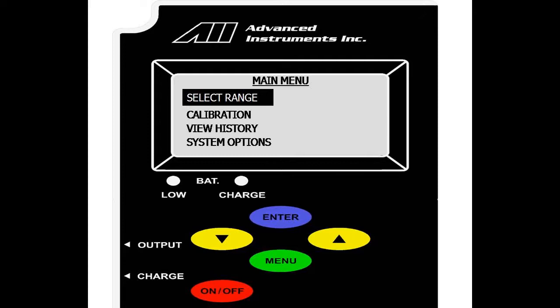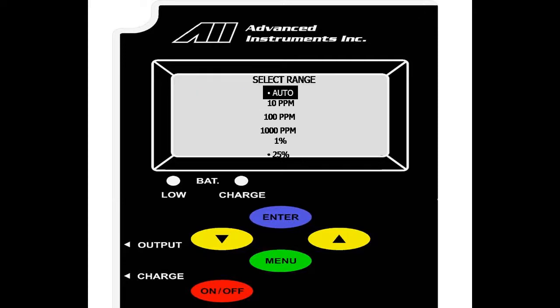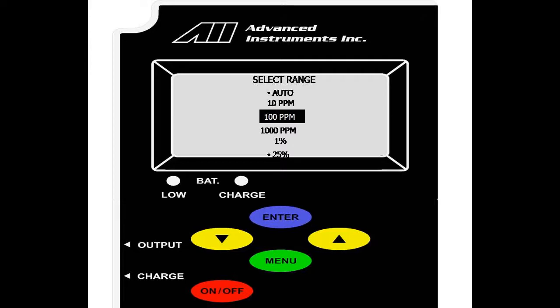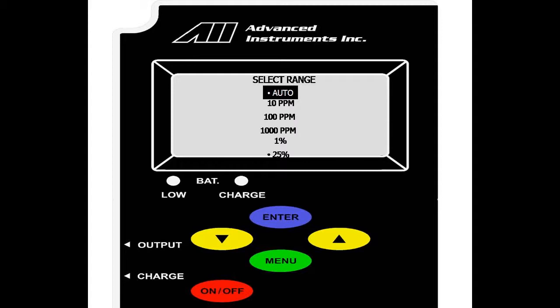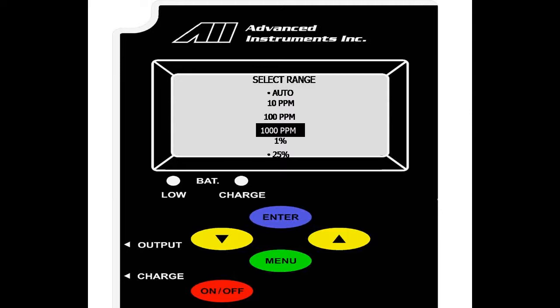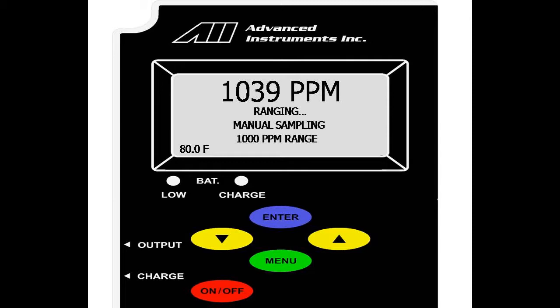We will now go over the range options. On the main menu, go to select range and hit enter. As you can see here, we have the five standard default ranges: 10, 100, 1000 parts per million, 1% and 25%. Currently, the analyzer is in auto ranging and at 25% indicated by the two dots. If we would like to select a fixed range and lock it as a manual range, say for 1,000 parts per million, we scroll down and select enter.